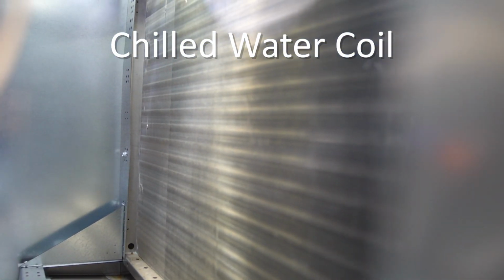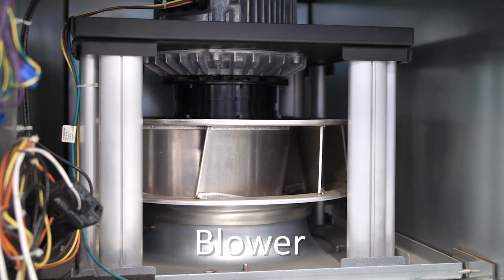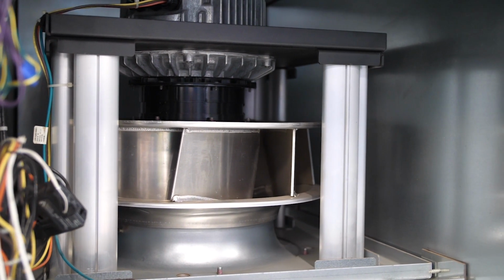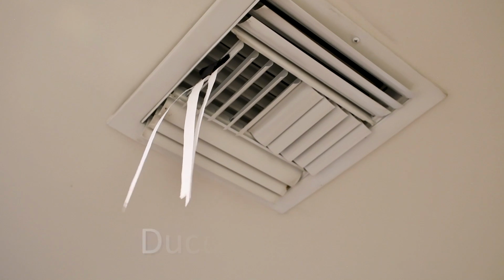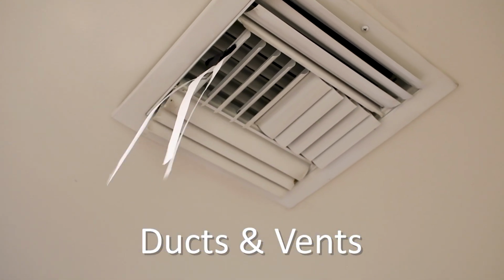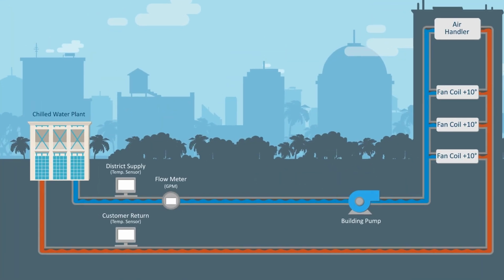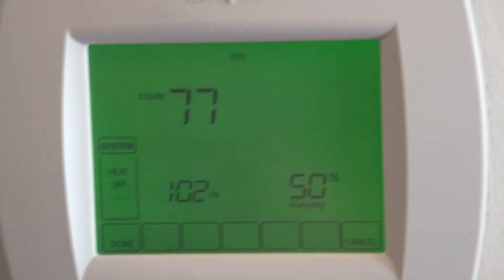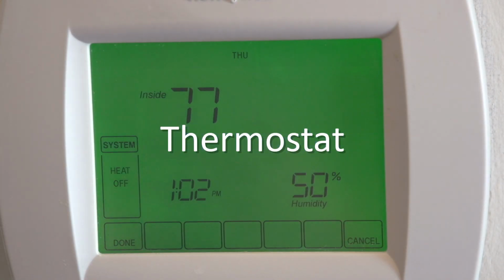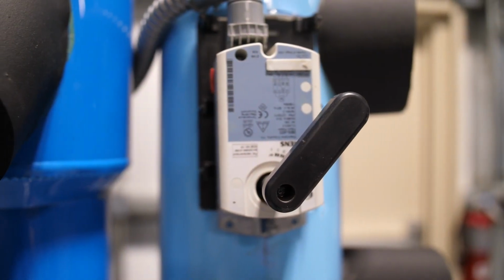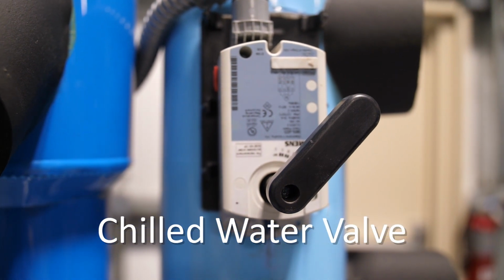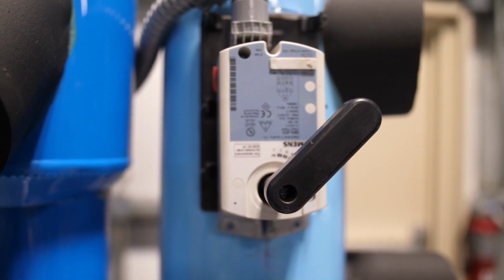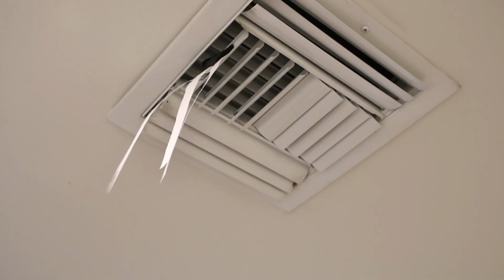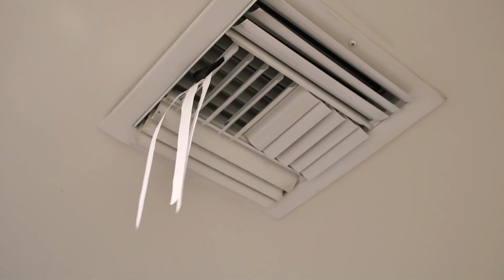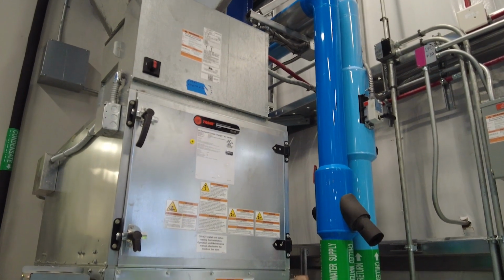Cold water flows through the coil while the blower sends warm air across it. The heat in the air is then transferred to the chilled water. Now you have cool air distributed to the ducts and vents in your living space, and warmer water leaving the building headed back to OUC. When the temperature in the room exceeds your cooling set point, the thermostat sends a signal to start the blower and open the chilled water valve. Chilled water flows and cool air conditions your space. When the temperature reaches your set point, the thermostat switches off the blower and closes the chilled water valve.